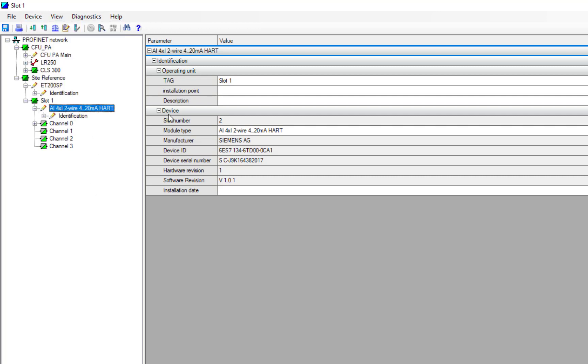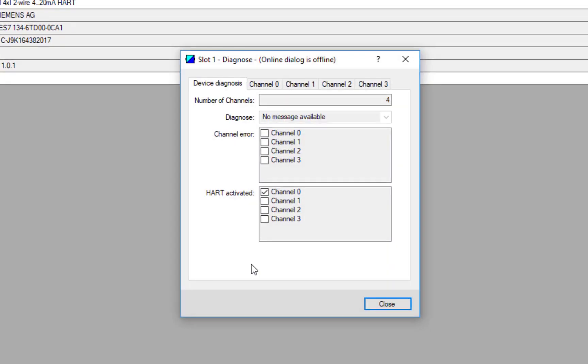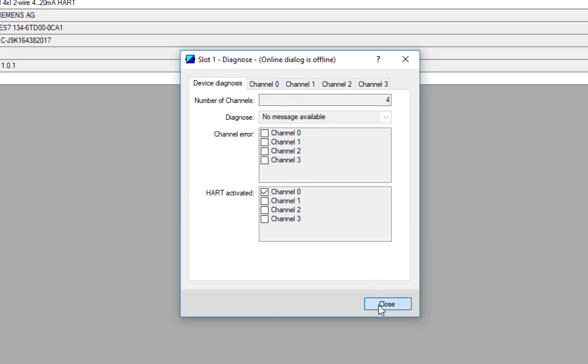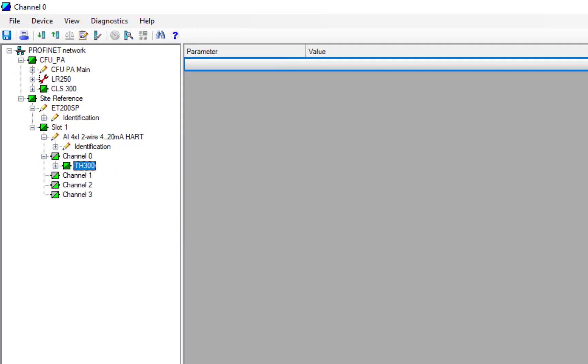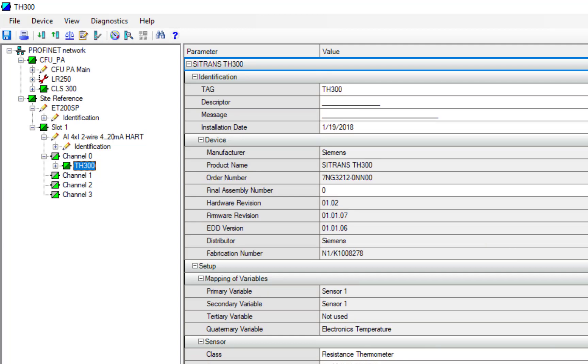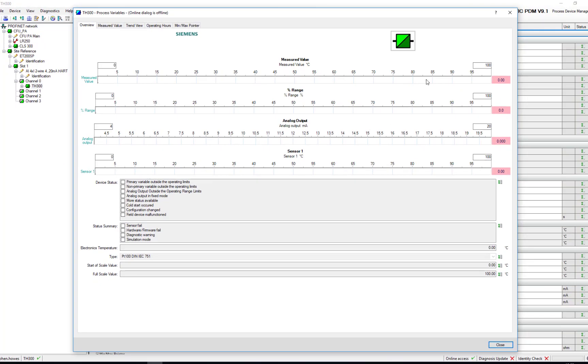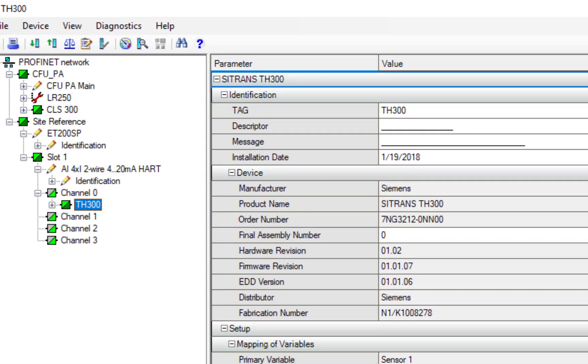So here we have the ET200SP slot 1. We'll go to diagnostics, I can update the diagnostics, I can check the configuration. I'm going to come down to the HART card. We'll have a look at the diagnostics for that. So I can see the HART is active on channel 0, and I have no wire breaks or measurement overrange or short circuits on that channel, so that channel's healthy. And then if I wanted to go a little bit further down onto channel 0, I can see the temperature puck and all of the parameters associated with that temperature puck. And I can also see the process values as they start updating on this screen. So it's very powerful once you have your network set up to jump from one instrument to another and see all of these settings.